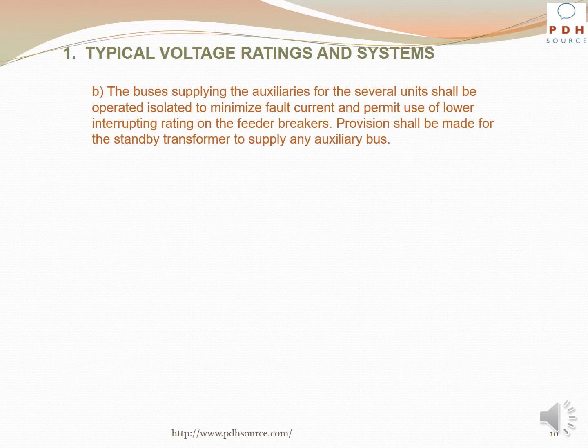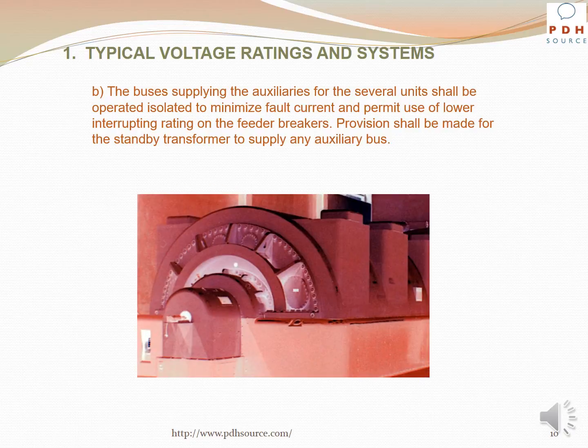The buses supplying the auxiliaries for the several units shall be operated isolated to minimize fault current and permit use of lower interrupting rating on the feeder breakers. Provision shall be made for the standby transformer to supply any auxiliary bus.